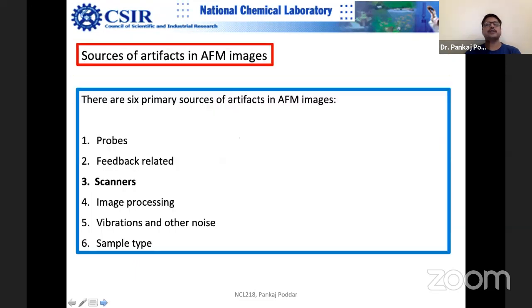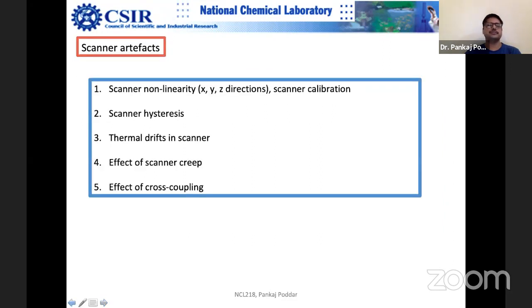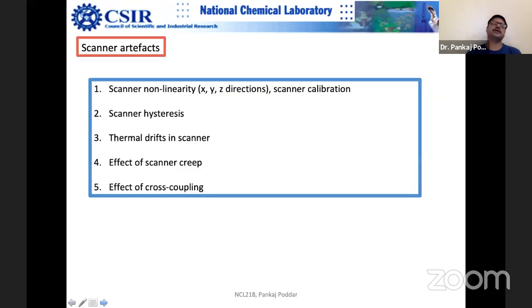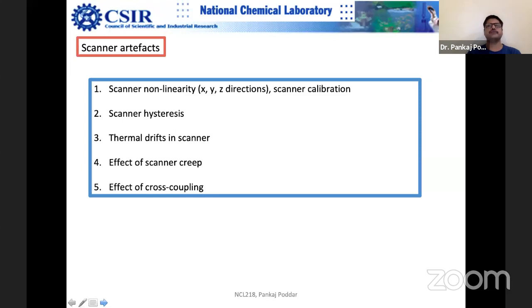Now, scanners. Scanners are a very important part and they have their own characteristics — aging, stresses, and nonlinearity. The scanner behavior can be described in two parts: one for X and Y, another for the Z direction. They are highly nonlinear. For example, when you apply 0 to 20 volts and the scanner is supposed to move 10 microns, if you apply only 2 volts (10 times lower), it will not move 1 micron as expected — this is because of high nonlinearity.